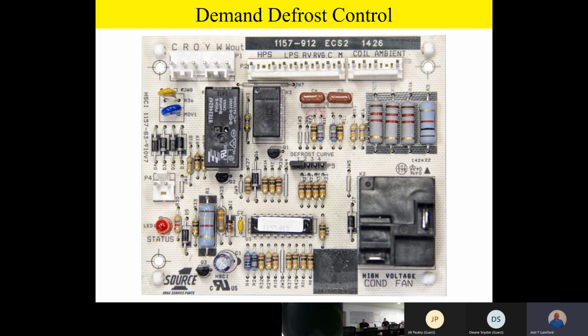Once that switch closes, it'll start a timing sequence, and it starts monitoring the run time on the outdoor unit. Then once a specific run time is met, and there's a field selectable jumper, by the way, typically 30, 60, and 90 minutes, once that time is met, wherever that jumper is set, 30, 60, or 90 minutes, once that time runs out, it'll then go ahead and go into a defrost. Once it goes into a defrost, it'll do the reversing valve. It'll go into cooling mode of operation, shuts the outdoor fan off, brings the auxiliary heat on so you don't freeze the homeowner out, and the thing is in defrost.